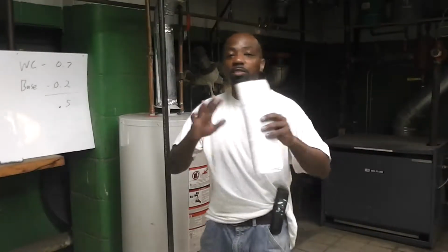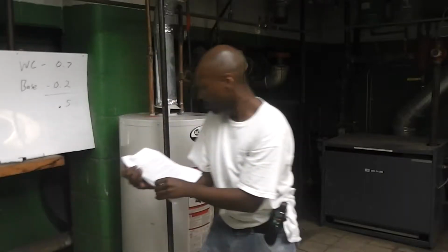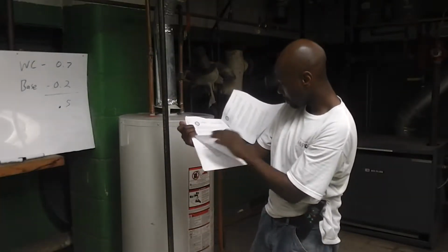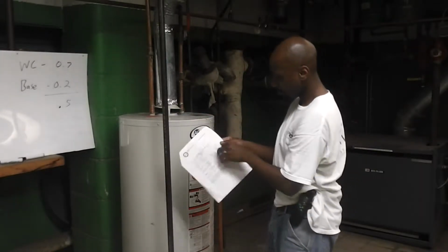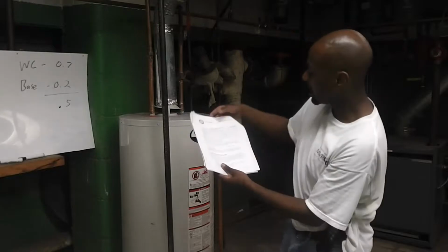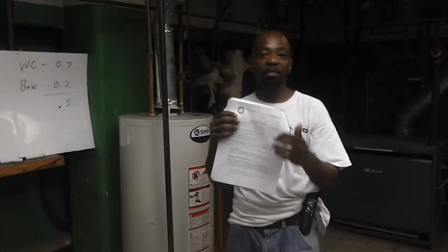Keep in mind, throughout this whole time, all the combustion appliances are off, so I'm not going to check that just yet. There we go. On page 14, there's a table that says CAZ depressurization limits. This lets me know how negative this place can be before it gets into a dangerous situation.